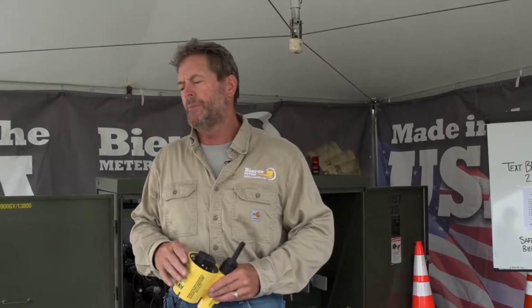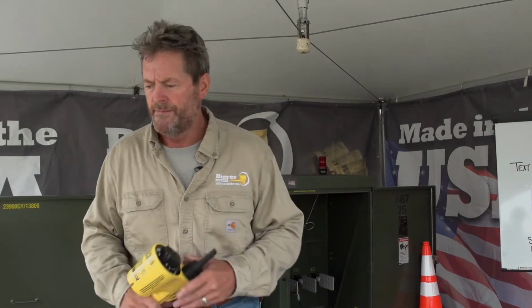As far as recalibration, that's up to the user. It really depends on whether you test your tool on a live known voltage source and you're getting accurate readings and results, then obviously your tools are calibrated. So we leave that up to the customer. We suggest once a year, but sometimes we get the tools in 15 years later and they need repaired and calibrated. So that's going to be your choice.